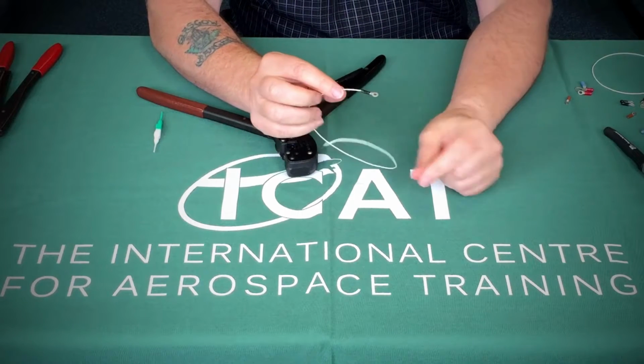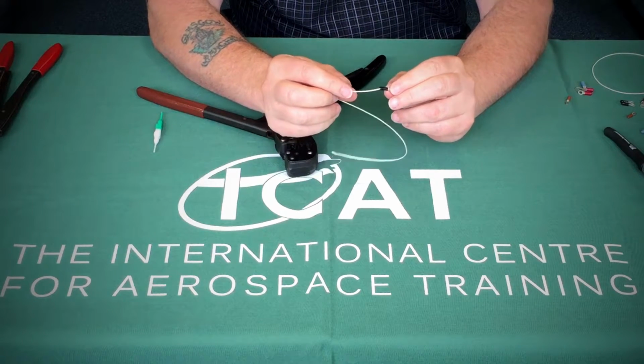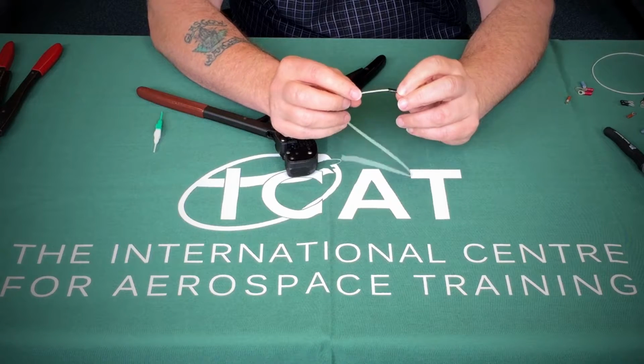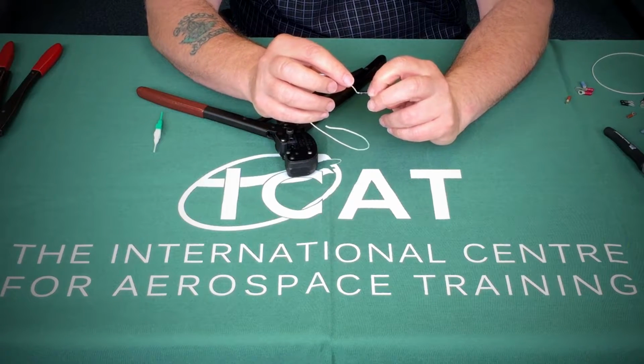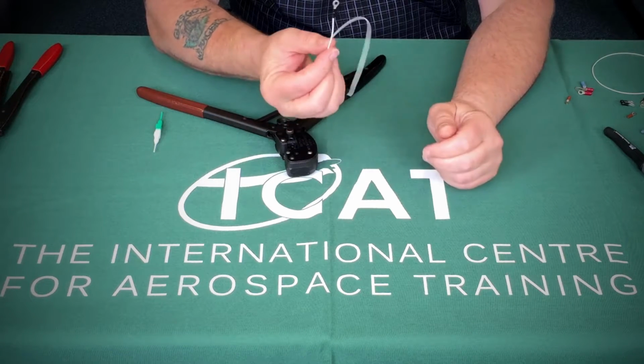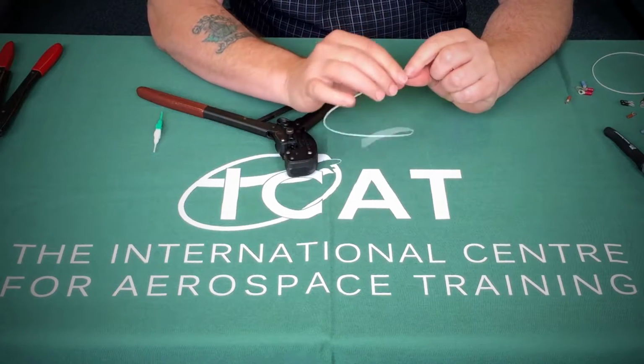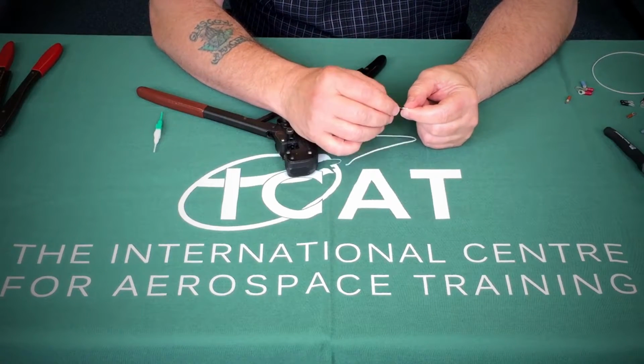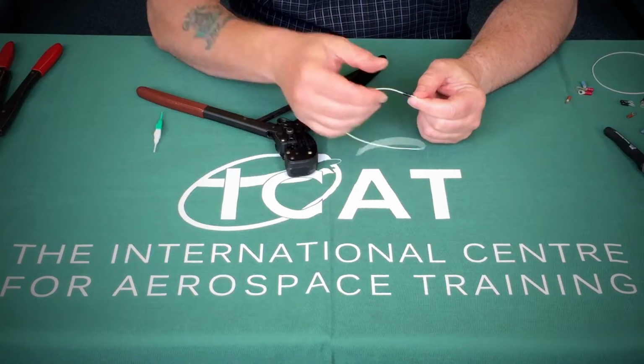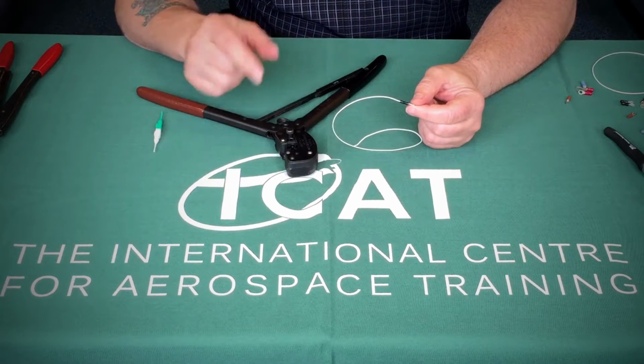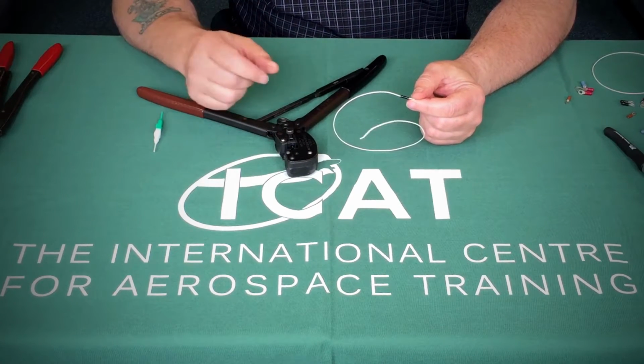Now in this position, you can see that the actual insulator has not formed away from the tool itself. What we should do now is just very gently move it 90 degrees in one direction, 90 degrees in the other direction. If the insulation does not pull out the crimp, then that means it is effectively supported within the crimp itself, and that is a good position for me to carry out my proper crimp.